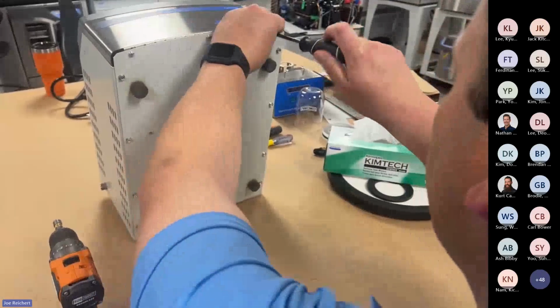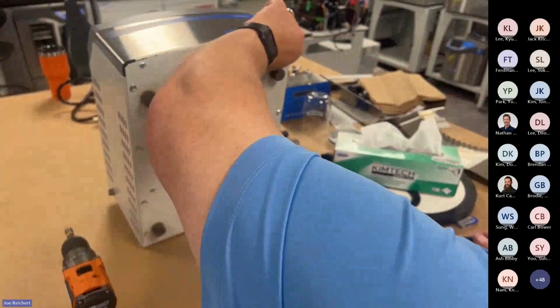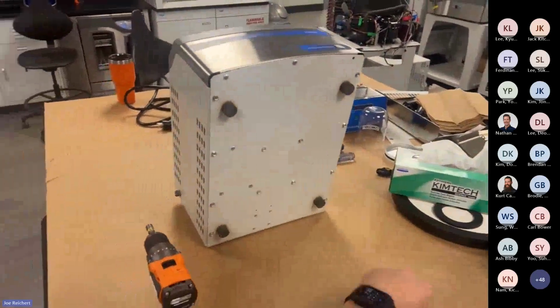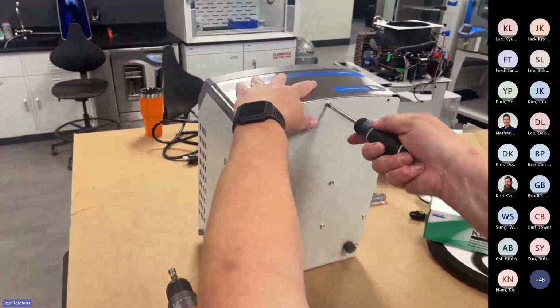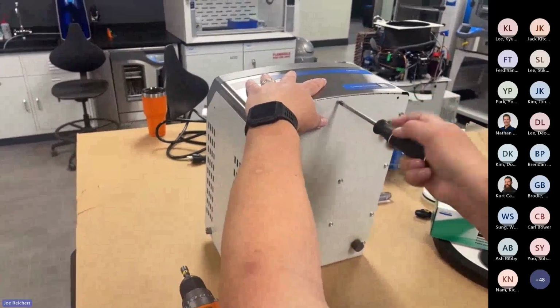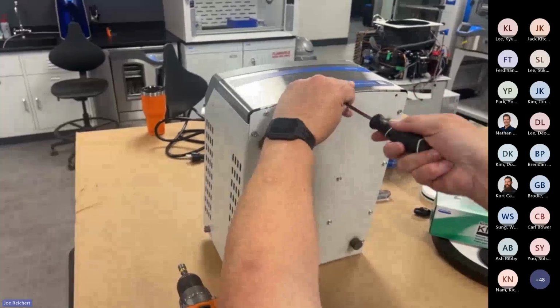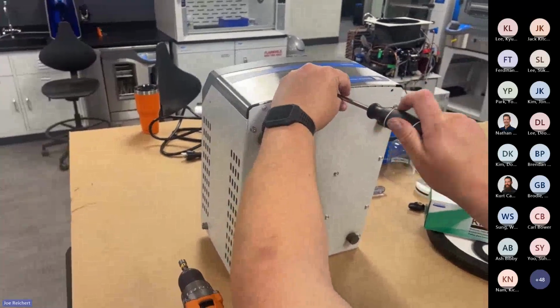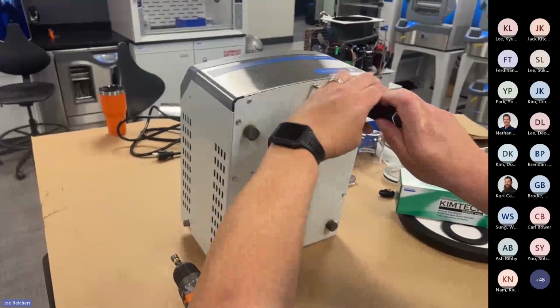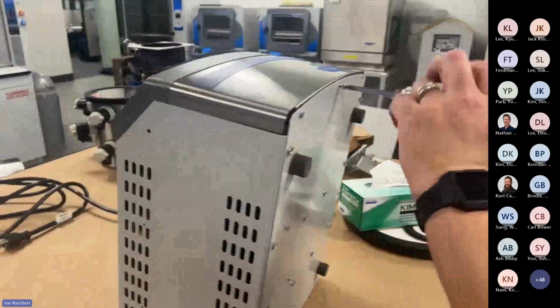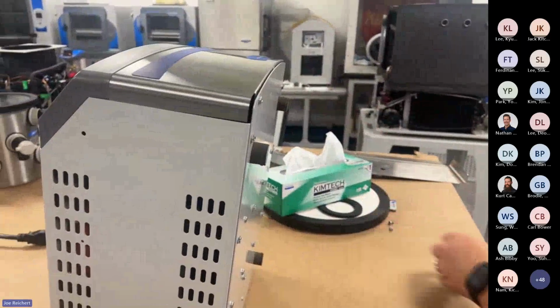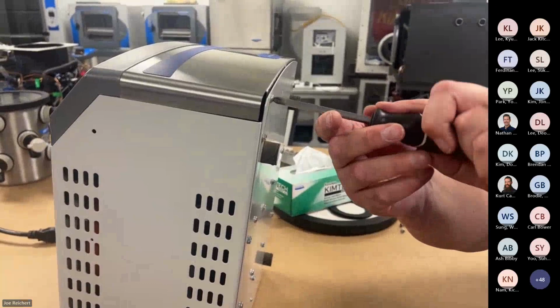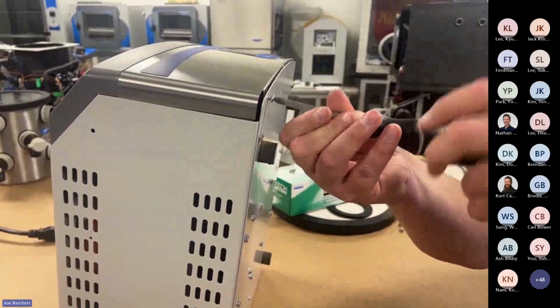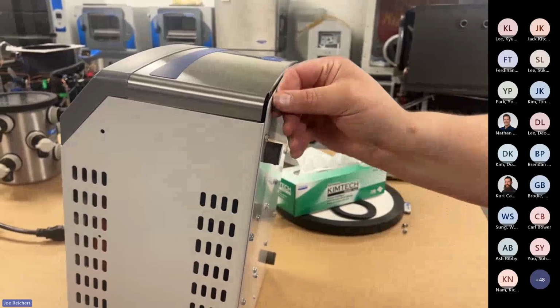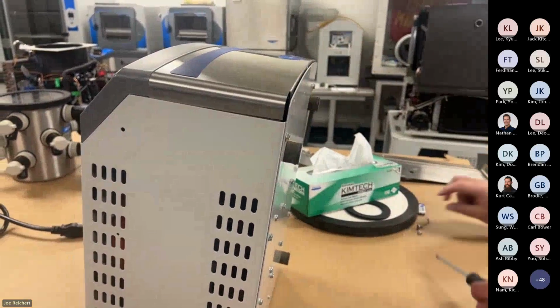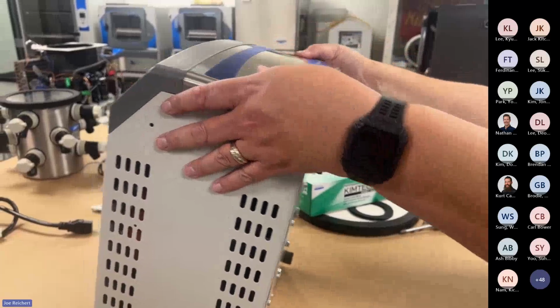Most of the issues you find with the CentriVap would be either that latch or with the bearings. Customers will buy the non-acid resistant unit and they'll use acids like acetic acid, something that's not really that you would think of as being corrosive. It doesn't hurt the chamber or the rotor, but it is not good on the bearings. So you can wear out the bearings. So you can get an alarm on this machine that says motor error, but I'll tell you that it is never the motor that is the issue.